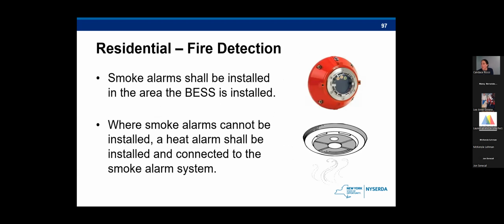Next is the fire detection requirement. You have to have smoke alarms installed in the area where the energy storage is installed. And if smoke alarms can't be installed, a heat alarm should be installed and connected to your smoke alarm system. So if you have a system that's located outside, it might be difficult to utilize a smoke detector. So a lot of those are using a heat detector system instead to recognize a temperature increase inside the system.